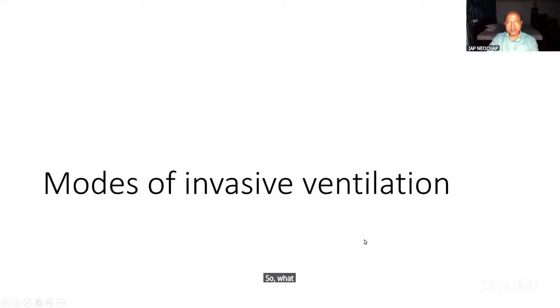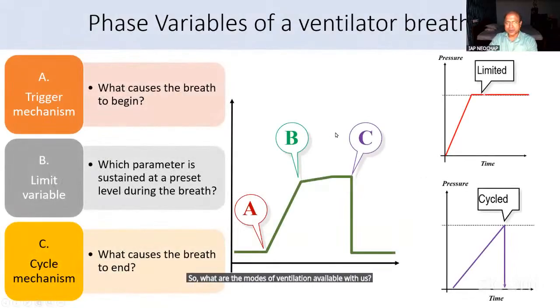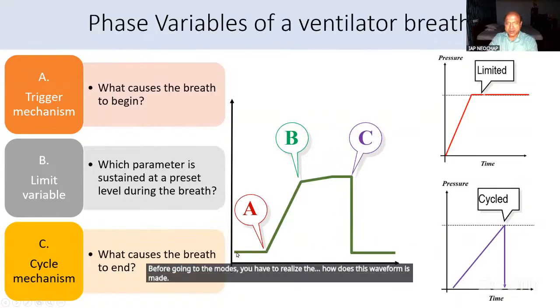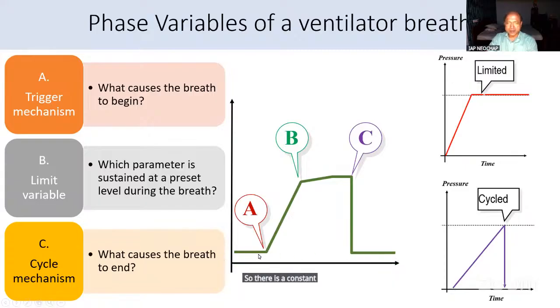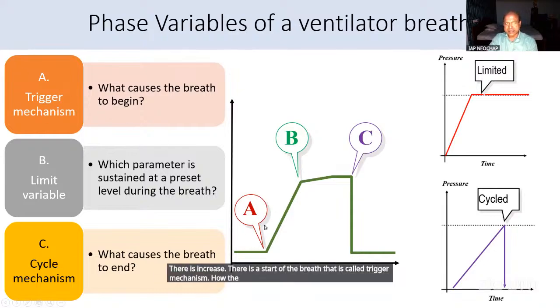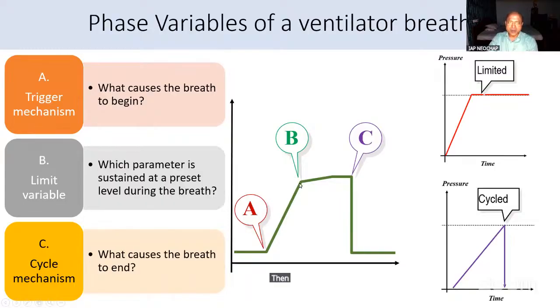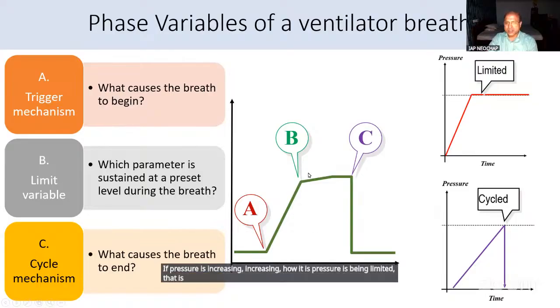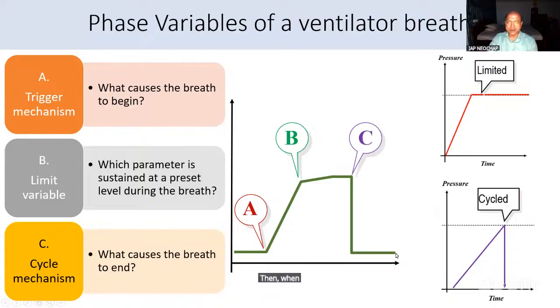So what are the modes of ventilation available with us? Before going to the modes, we have to realize how this waveform is made. So there is a constant pressure in the tube, that is PEEP. Then there is a start of the breath, that is called the trigger mechanism, how the breath is being triggered. Then, if pressure is increasing, how the pressure is being limited, that is the limit. Then when the pressure starts coming down, that is cycling. How is it being cycled?